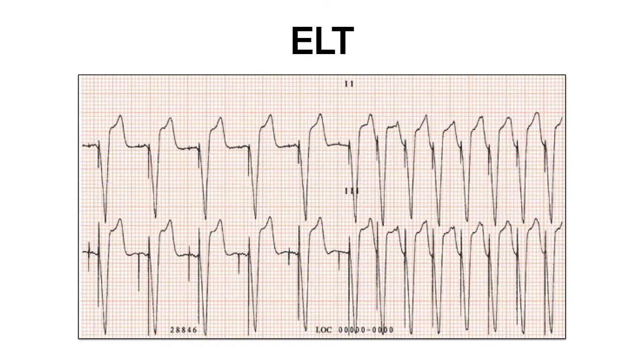The extension of the PVARP also will help in preventing this kind of arrhythmia. Some pacemakers have the adaptive PVARP in the rate responsive modes, and the shortening of the AV interval after a single beat to induce a retrograde VA block is one of the methods that can be programmed in the pacemaker. Also, some pacemakers have a function of dropping ventricular paced beats if the pacemaker is pacing at the maximum tracking rate for a specific period of time. All of these methods might terminate and minimize the occurrence of the endless loop tachycardia.